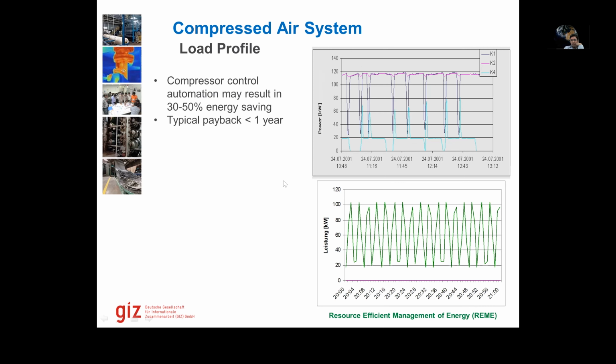Then this single compressor system, as you can see, is only going on load shortly, then going off load, on load, off load. This seems to be an oversized compressor whose demand is very low, and it's just going into on load and off load. So all this offload time, it's only consuming energy but not really contributing. A typical case where a variable frequency drive can be installed, and we can easily modulate this one because it's a single compressor system.